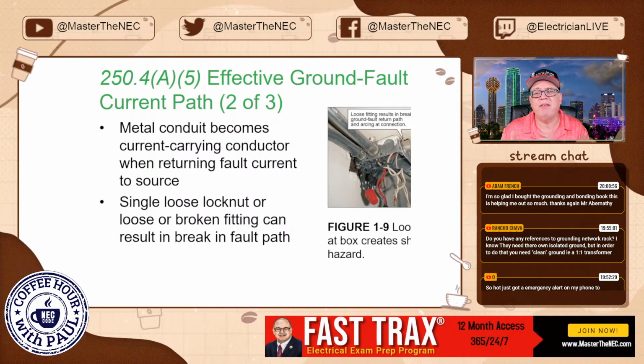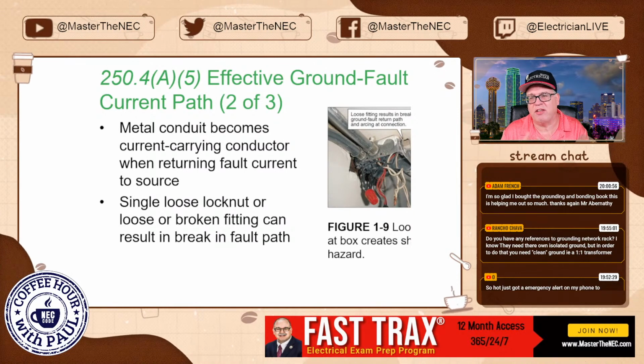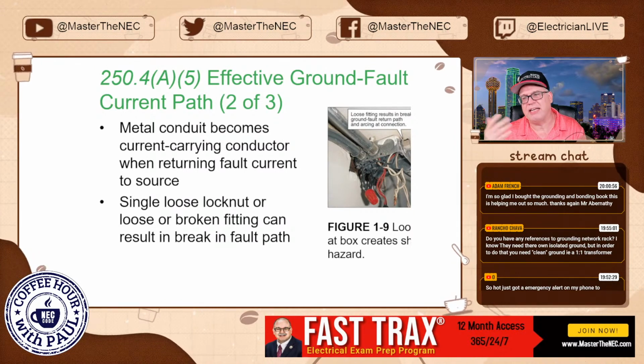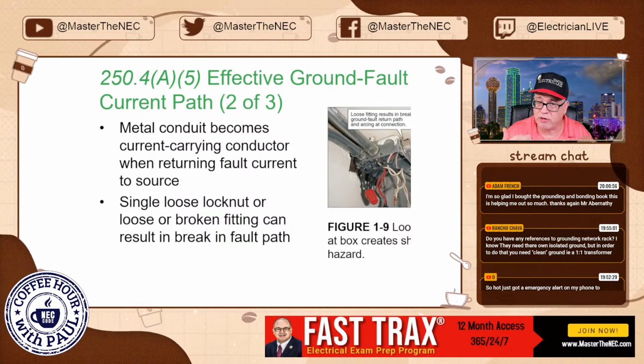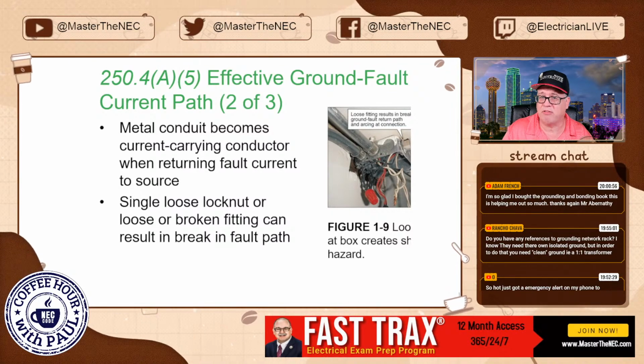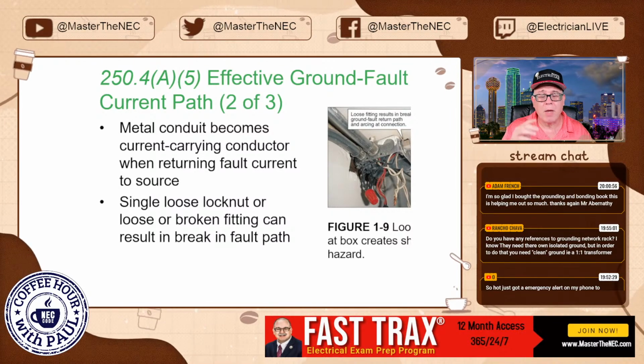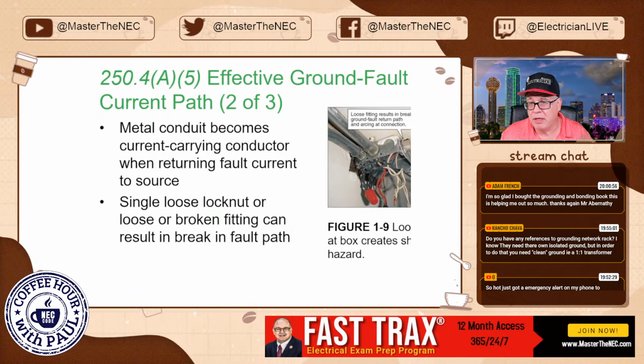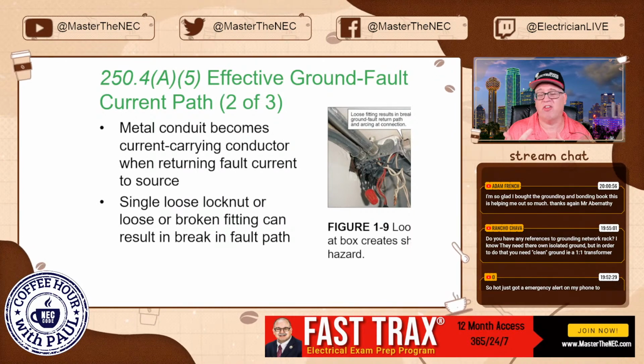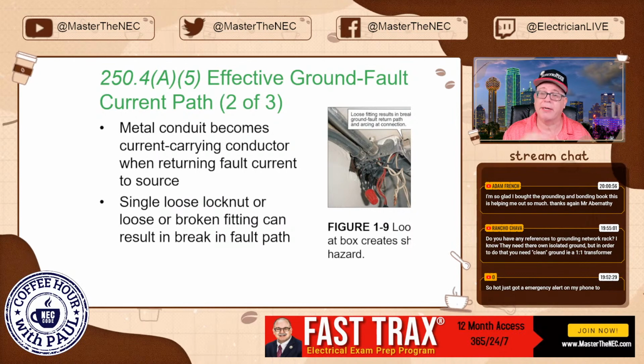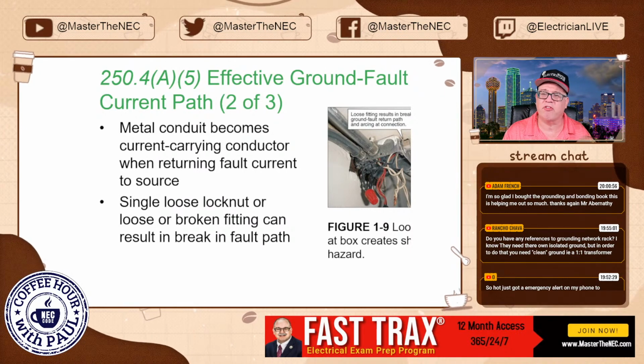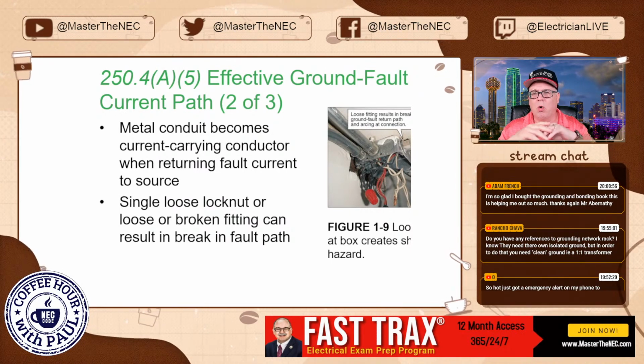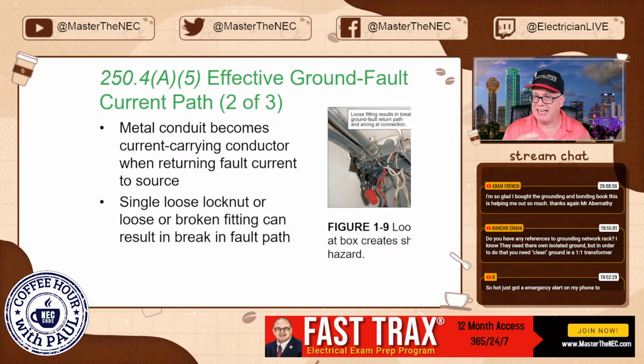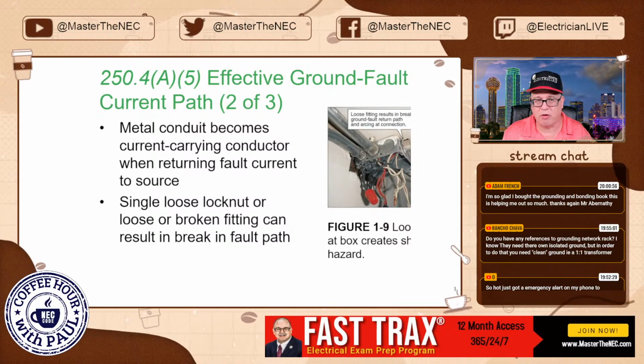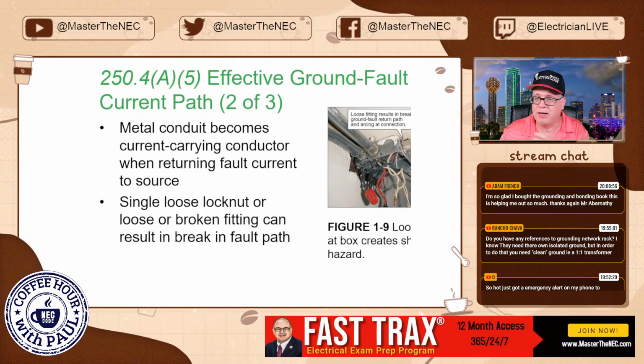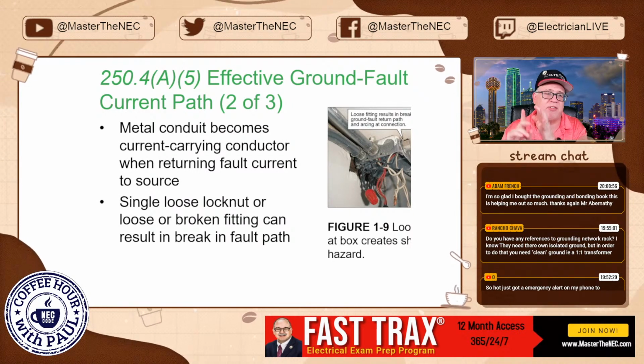Now, what happens is typically, in this case, in the illustration, you see that it looks like it is using the raceway as an equipment grounding conductor. And 250.118 allows me to do this. Okay. But if you have a wire type equipment ground in there and it's bonded to this box properly, because there are splices here, so it's bonded to the box, then chances are if the raceway or the box is energized, then you've got that wire type low impedance. You don't have to worry about somebody having a loose fitting, a loose connection, somebody didn't tighten the set screw.